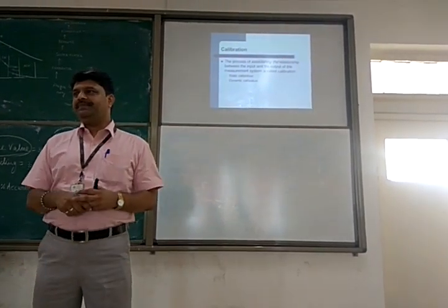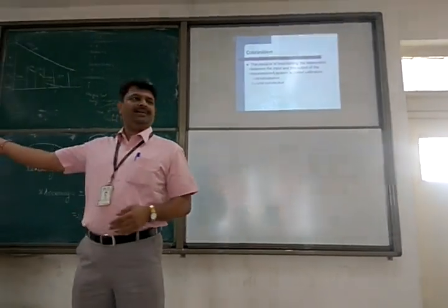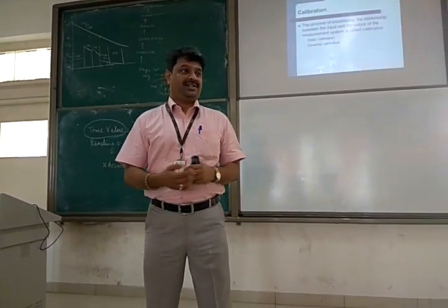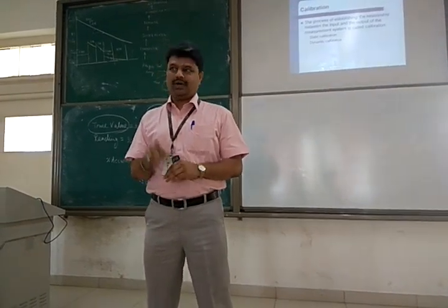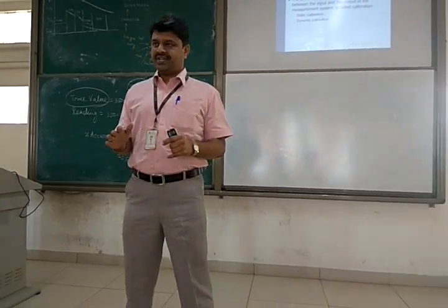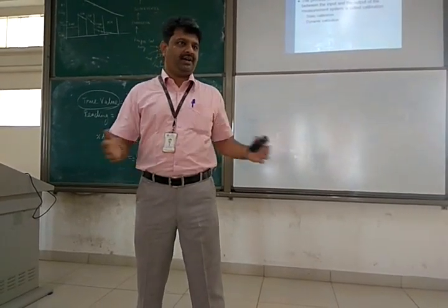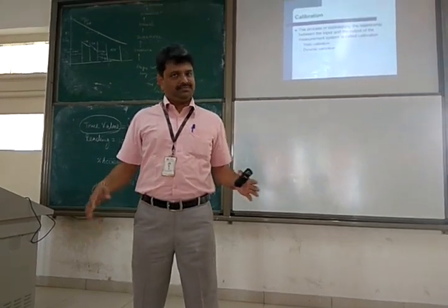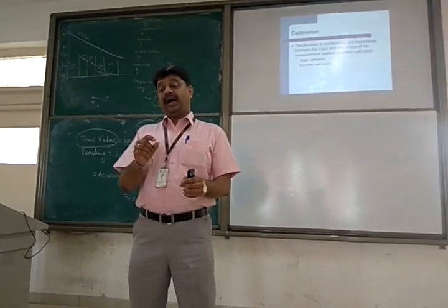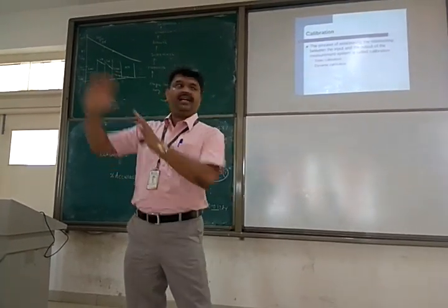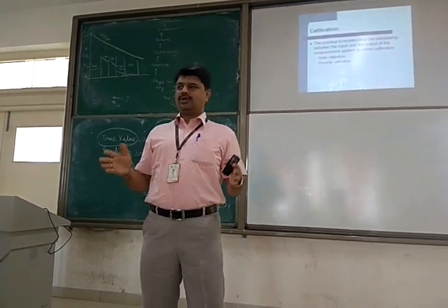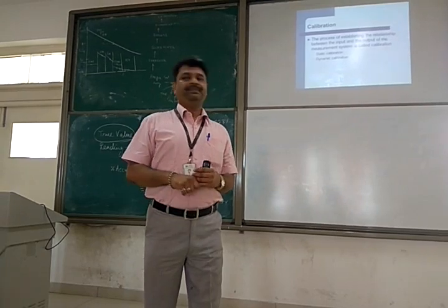But if you go to industry, you say, hey, send this instrument for calibration. That is called recalibration. There is calibration and recalibration. First we talk about calibration. In industries, suppose you are an engineer in a manufacturing company and you bought some instrument and used it for 6 months. After 6 months it is supposed to be calibrated. You send the instrument for calibration. What you are basically doing is recalibration. They also call it calibration, but that's recalibration.